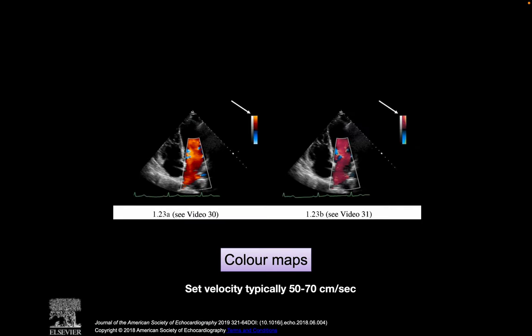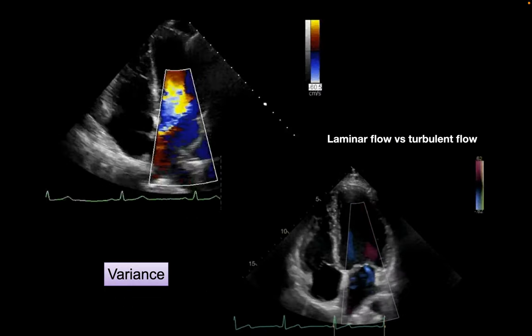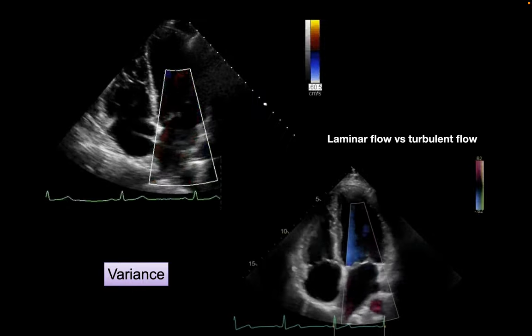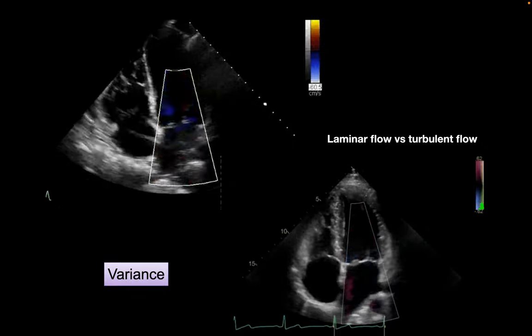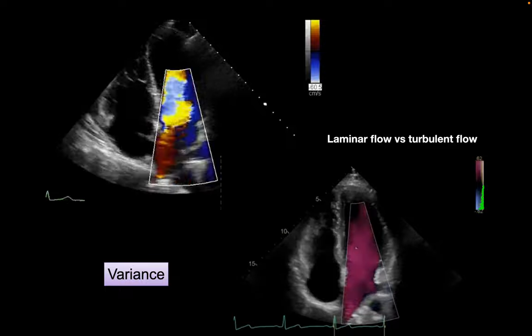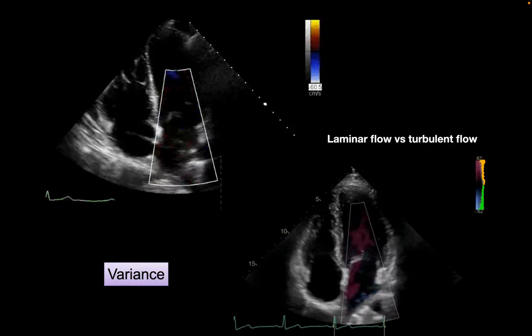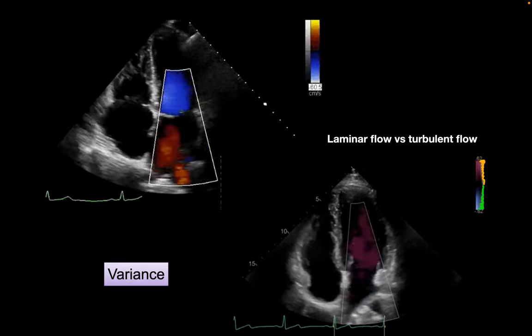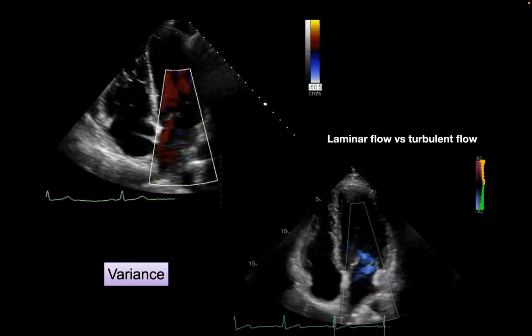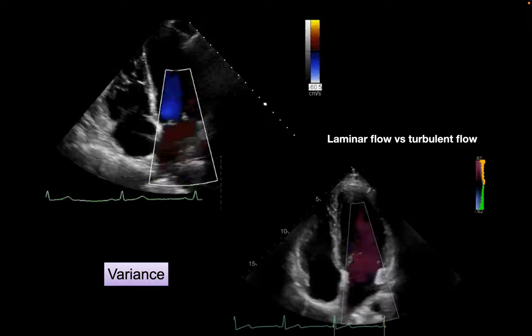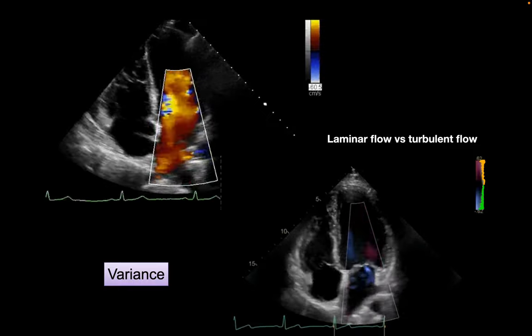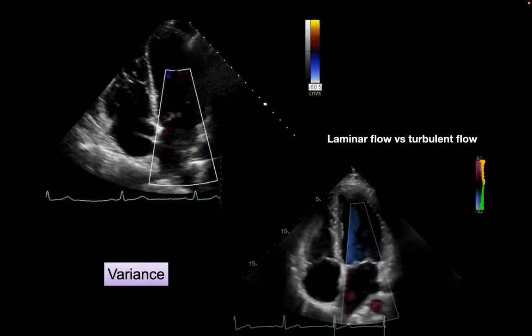You can use various color maps, and again it means that different hues of different colors will be used for those blood flows and movements. The velocity we usually set between 50 to 70 centimeters per second, and if you use variance, it means that turbulent looking flows will be assigned greens and shades of greens and yellows. So it's just one way for us to tell that turbulent flow is occurring in that area. Otherwise you will just get that mosaic looking flow. So when there is a turbulent flow, you'll get blues and reds right next to each other.